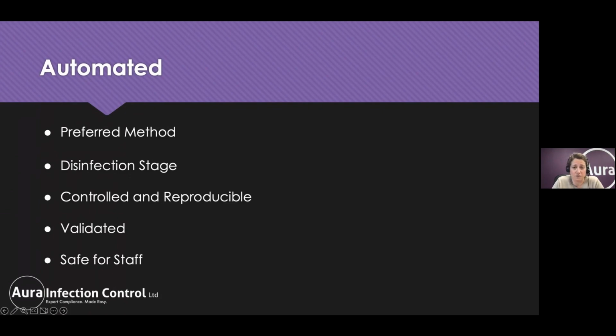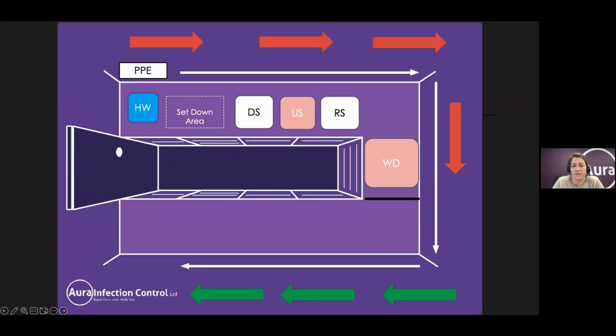Data loggers can record this, and the printout, whether printed off or data logged, allows you to sign off that each batch of instruments has been subjected to the parameters required for disinfection. That means that we have evidence, and that's a validated process. It's much safer for staff as well. So we can pop our washer disinfector in. Our cleaning processes are completed.